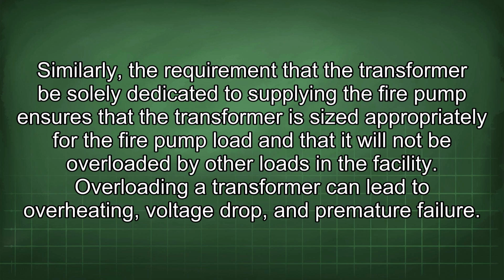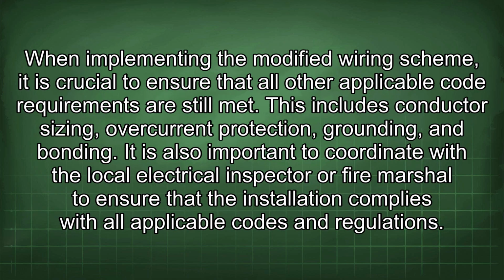Similarly, the requirement that the transformer be solely dedicated to supplying the fire pump ensures that the transformer is sized appropriately for the fire pump load and that it will not be overloaded by other loads in the facility. Overloading a transformer can lead to overheating, voltage drop, and premature failure. When implementing the modified wiring scheme, it is crucial to ensure that all other applicable code requirements are still met. This includes conductor sizing, overcurrent protection, grounding, and bonding. It is also important to coordinate with the local electrical inspector or fire marshal to ensure that the installation complies with all applicable codes and regulations.